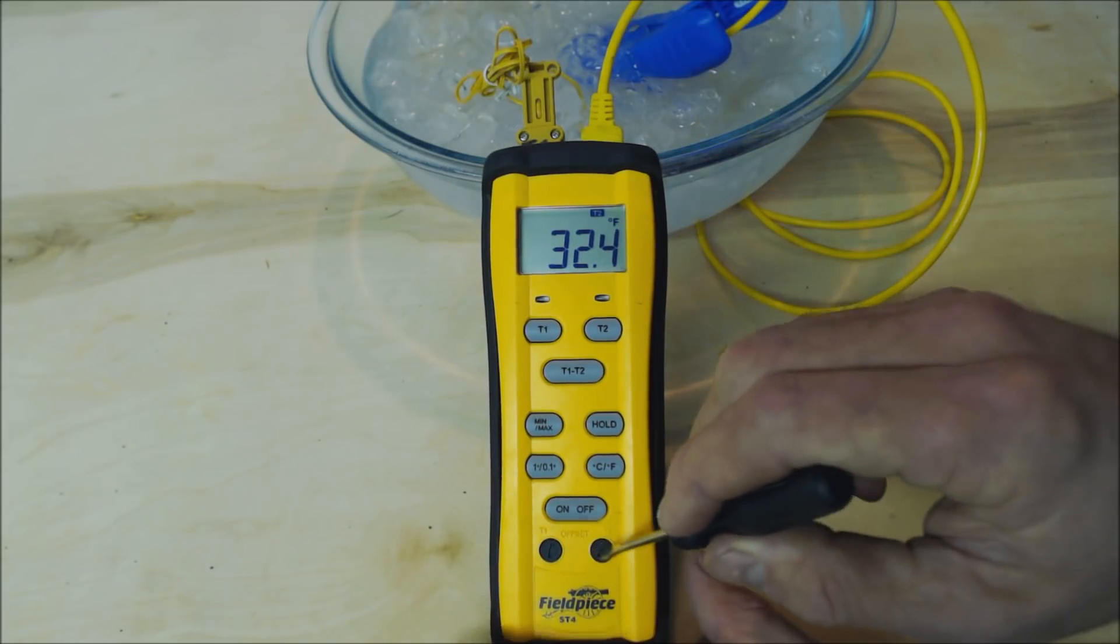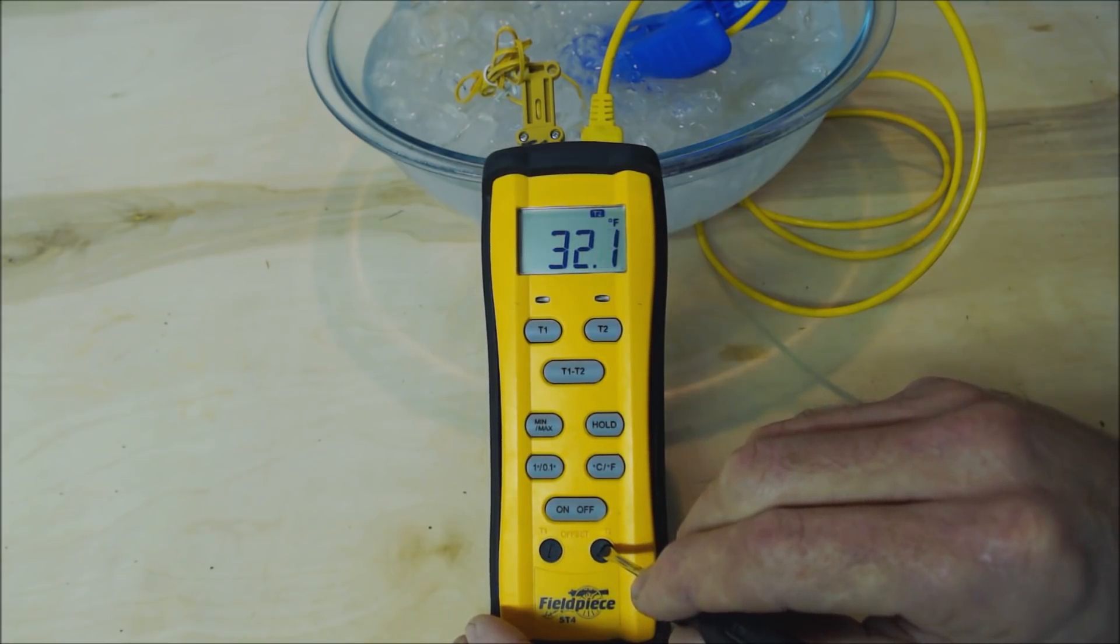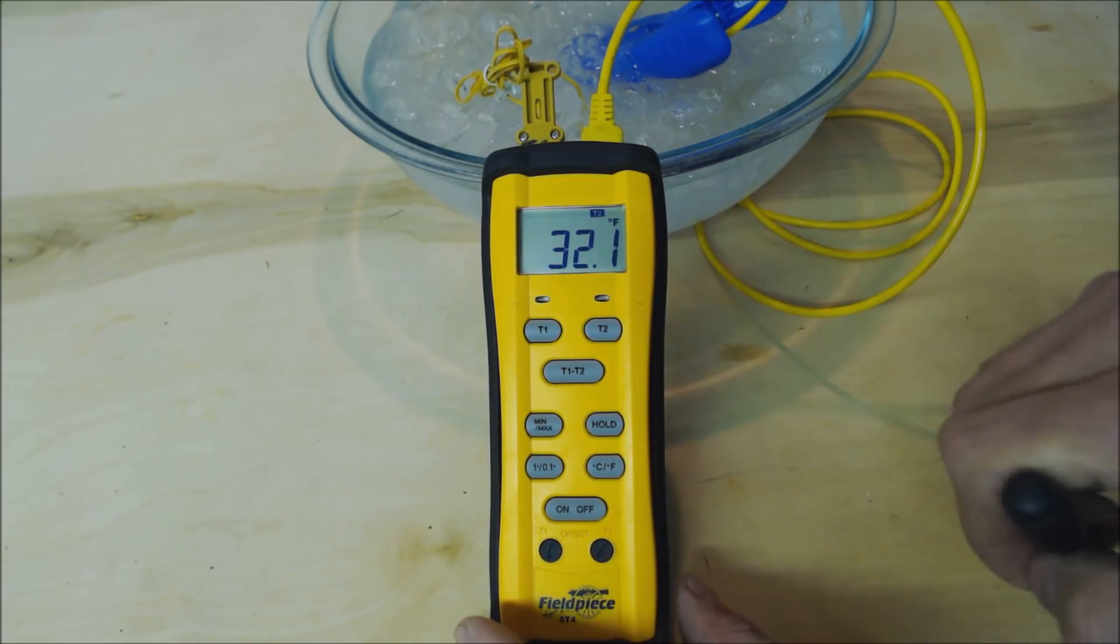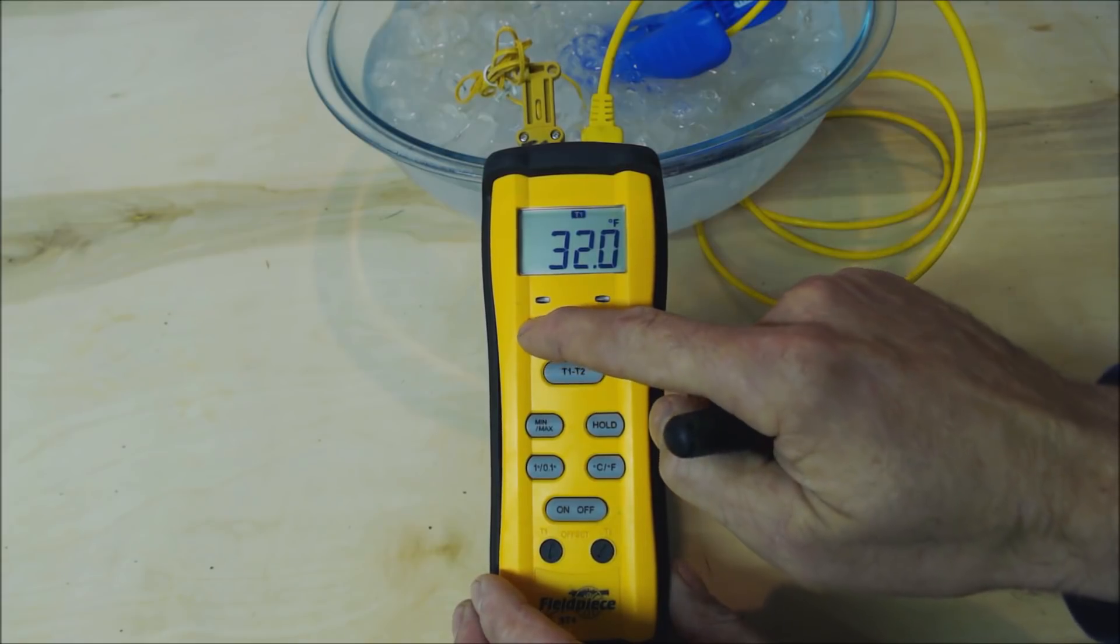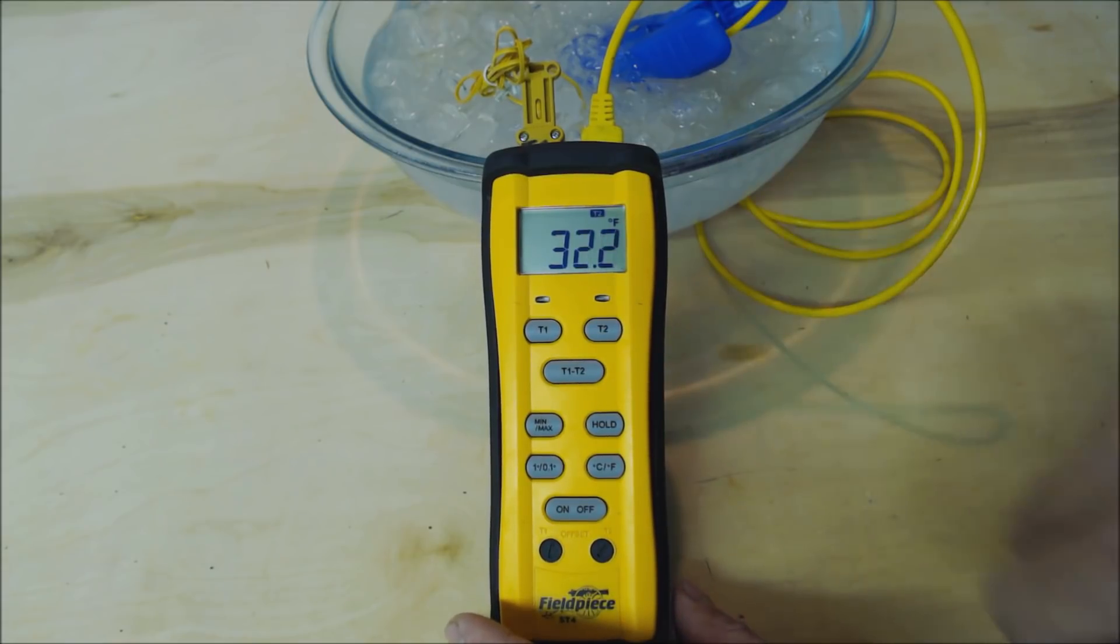So now we'll just adjust our T2. We're just going to turn it clockwise until we get to 32 degrees which we're there now. Now also you want to check your T1 just to make sure that there's no change in that as well. And that's how you do it.